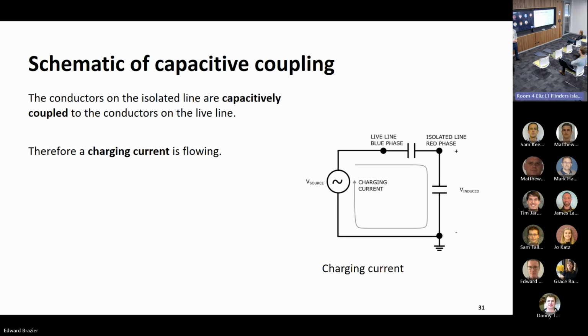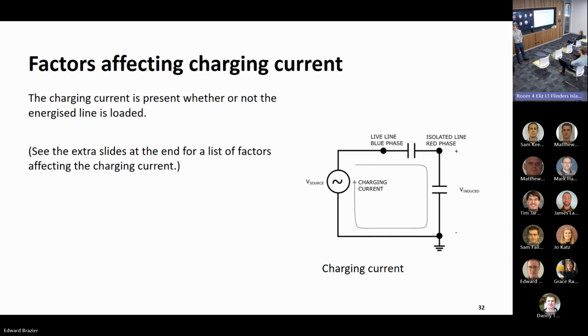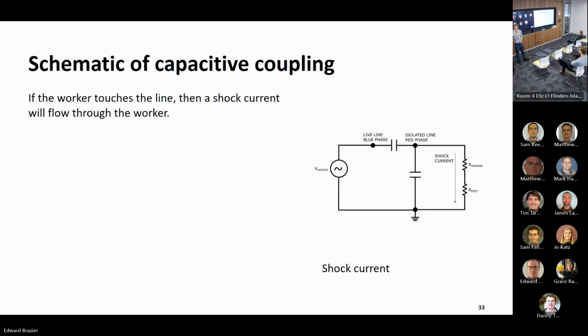Because of these capacitances, we have a capacitive charging current flowing. That means that if a worker touches the isolated conductor, the charging current will flow through the worker. That charging current is present whether or not the live line is loaded. Even if the live line is just energized, but there's no load at the end, you'll still get this effect where if a worker touches it, charging current will flow through the worker.